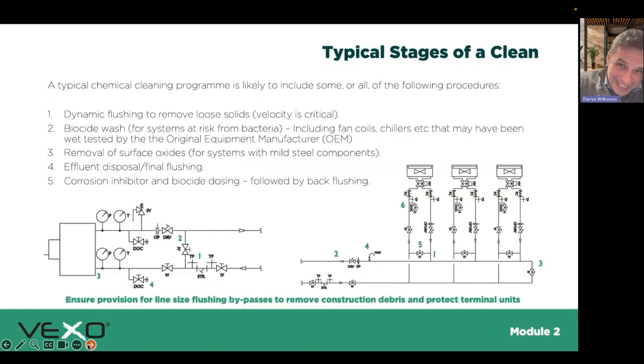And then we have the different stages of the clean to consider. When the system's first filled, generally it's recommended it's filled with treated water, rather than raw water. And you don't want to fill a system and then drain it once you've filled it. It actually makes things a lot worse. But typically the approach the water treatment company will take is dynamic flushing. This is where they would take terminal units and put them into a bypass situation before you even run those pumps. Once you've got those pumps running and everything's in bypass, they would then look to dynamically flush, which means they look at the velocity. So they would plug on a manometer and check that they're achieving the flow rates across the horizontal branches of the pipework. So anything up to 5 millimeters in size will be moved.